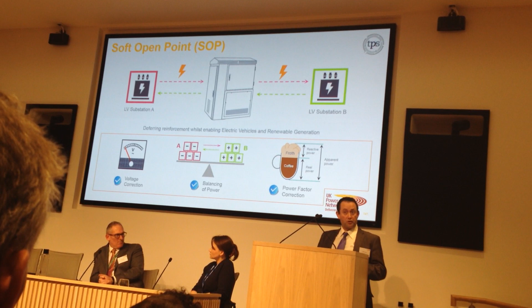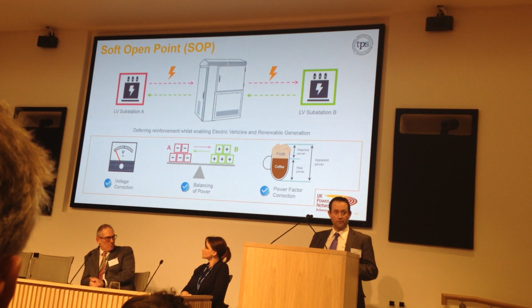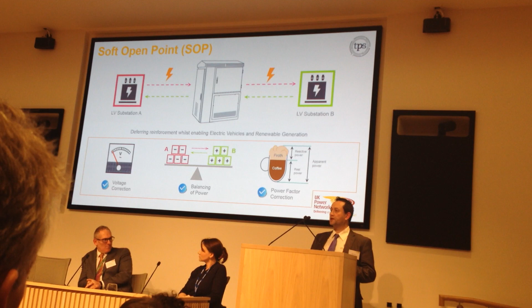Being power electronics, we have control over both active and reactive power. Having control over reactive power, having meshed two points of the network, we can control those nodes to manage voltage, so we can do voltage correction. With reactive and active power control, you can do power factor correction. It's a fast device, but all power electronics is very fast, so we can actually cancel harmonics in the network as well.